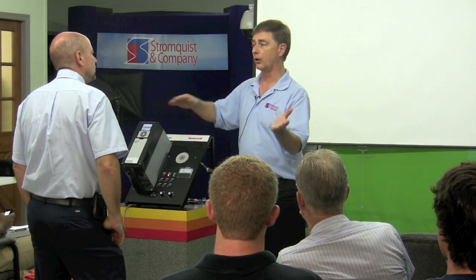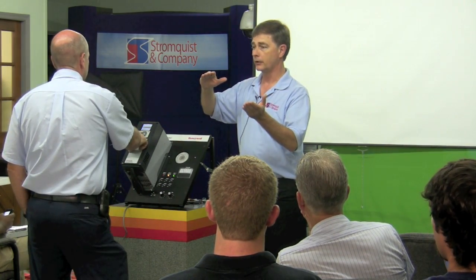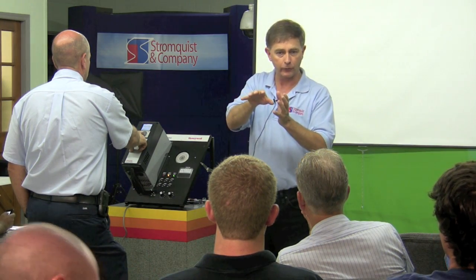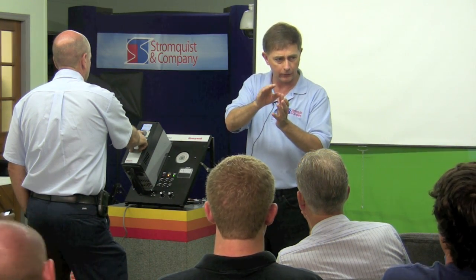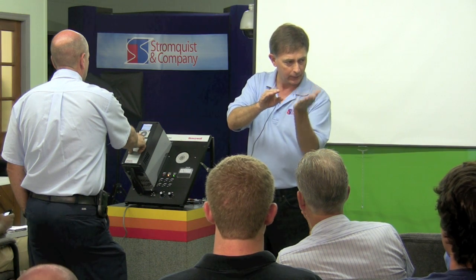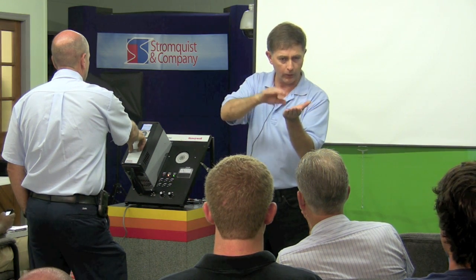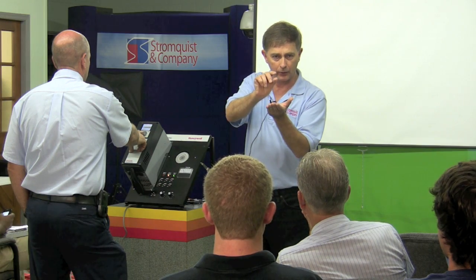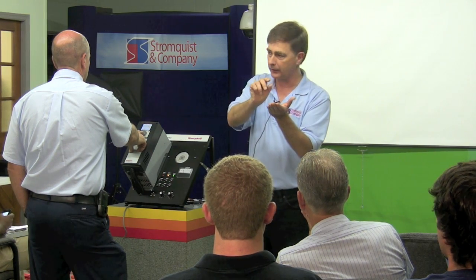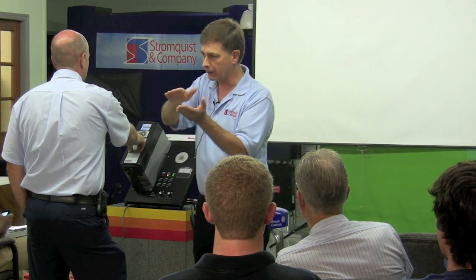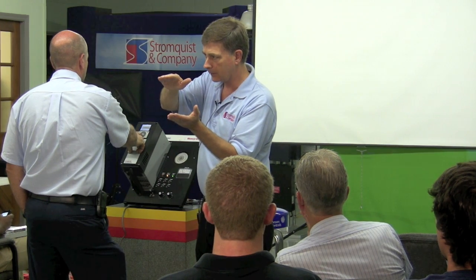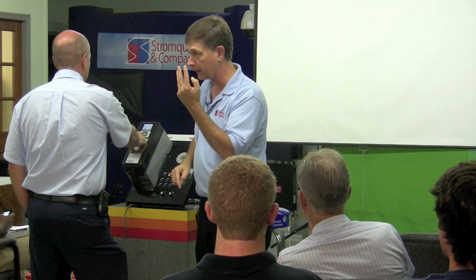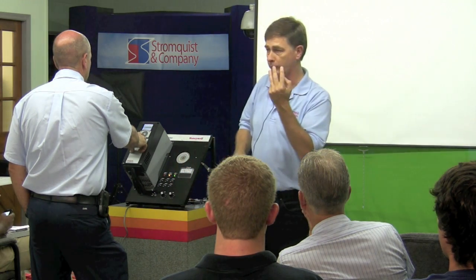What you'll need to do is have a low and a high. So if you mask out — let's say 25 is your problem frequency, you get a little shimmy there — you'll want to say low limit is 24, high limit is 26, unless the problem has a little bit wider spread. You want to be surrounding that problem, mask it out. You can have up to three of those prohibit frequencies.